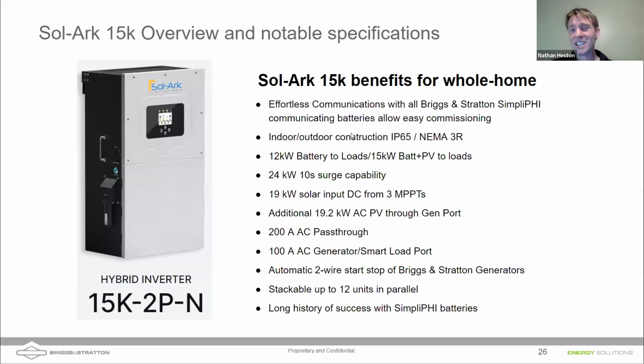19 kilowatts of DC coupled solar from 3 different MPPTs. This means you could have 3 independently controlled maximum power point tracking devices to bring your solar in. You can additionally bring in another 19.2 kilowatts of AC coupled solar. And again, these two do not influence each other. If you bring in 19 kilowatts from the DC side, you can still bring in another 19 from the AC coupled PV through the gen port.